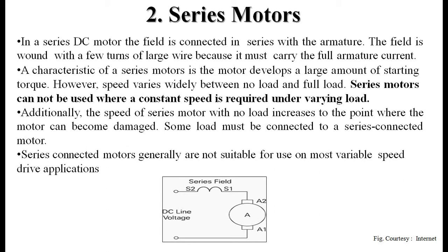Series motors cannot be used where constant speed is required under varying load. Additionally, the speed of a series motor at no load increases to the point where the motor can become damaged, so we cannot run this type of motor under no-load conditions. Some load must always be connected to series motors. Series connected motors are generally not suitable for most variable speed drive applications.